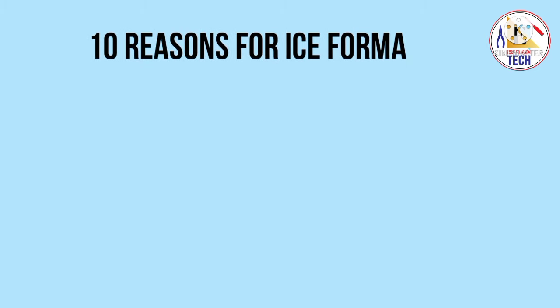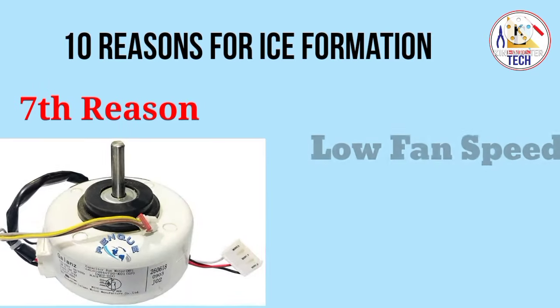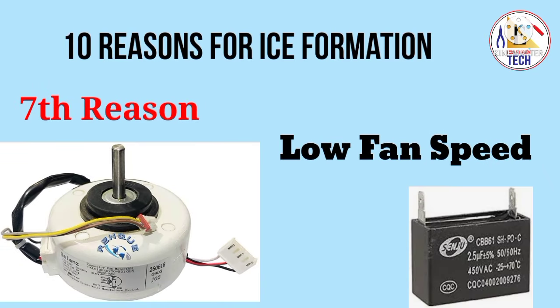The seventh reason is low fan speed. If the capacitor of our indoor fan motor is weak, we get low speed and there will be ice formation in the indoor unit. Even if the fan blower or motor is not in good condition, there will also be ice formation.